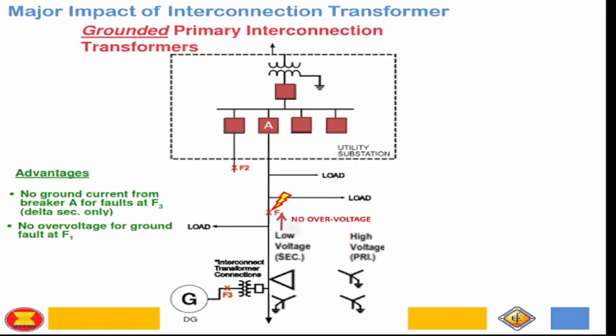No overvoltage. Okay? Because we all know that in a grounded system, the behavior changes. I mean, if phase A is faulted in a grounded system, only that phase will have a rise in fault current. The voltage will dip, but the other phases remain constant, or healthy. So that is its characteristic. Then, no overvoltage in that scenario.